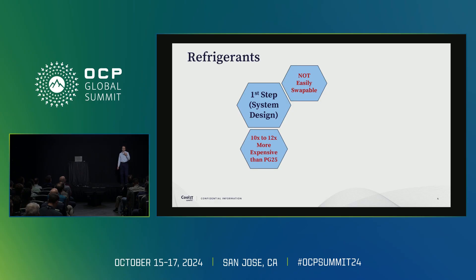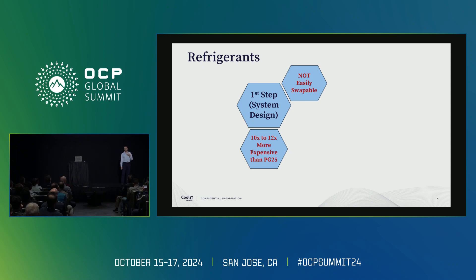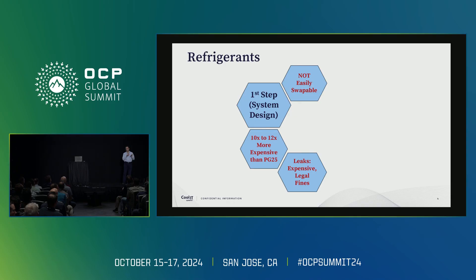You also have to consider the cost of refrigerants — one kilogram of refrigerant compared to PG25 water-based solutions is 10 to 12 times more expensive. If you are looking at gallons and gallons of refrigerant, the cost would be highly significant as an initial investment. Then imagine if there is a leak — the servers won't be damaged, but you risk losing your entire highly pressurized refrigerant into the environment. You lose significant money, and you face legal fees because there are local and federal laws about leaking refrigerants — typically anything above 10 kilograms must be reported to the relevant ministry, with significant legal consequences.